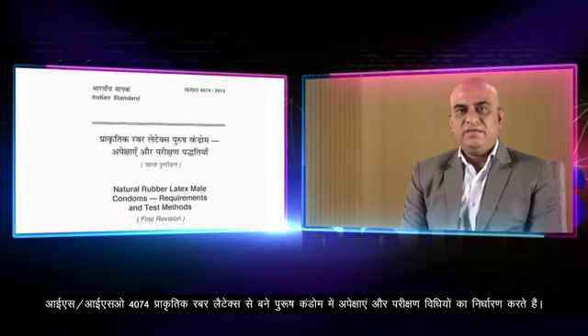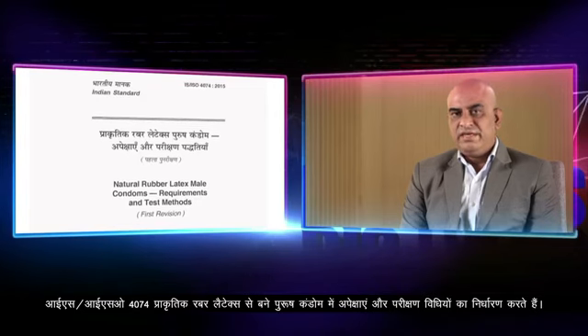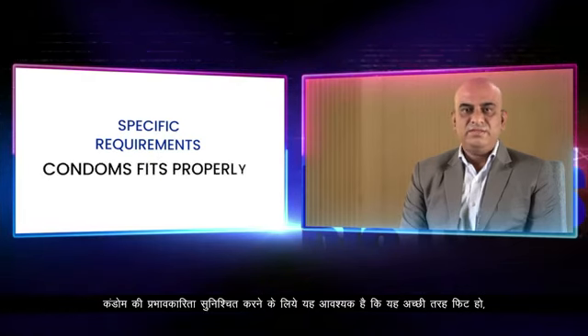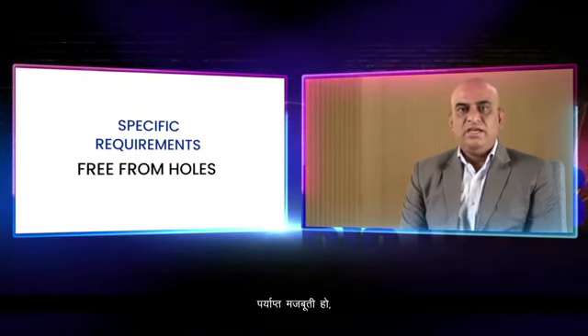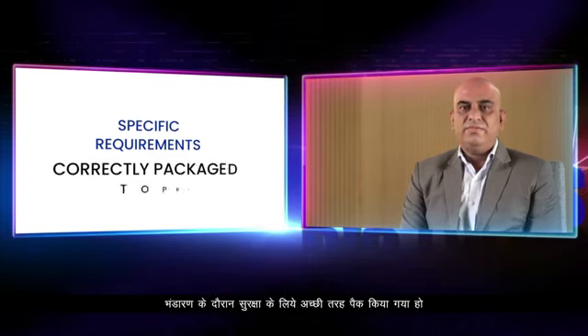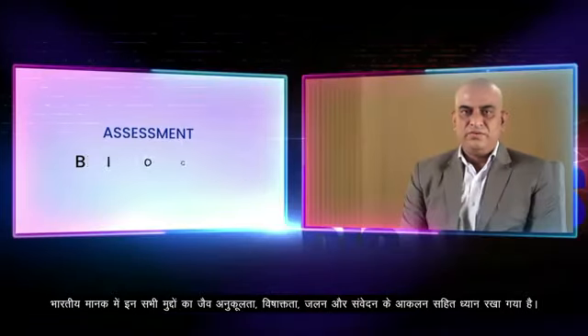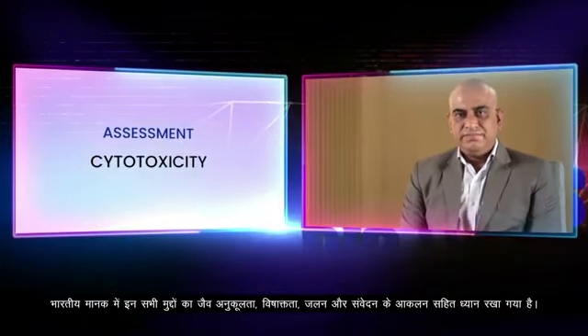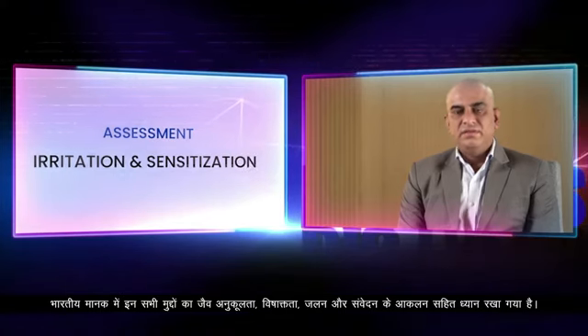ISO 4074 specifies the requirement and test methods for male condoms made from natural rubber latex. To ensure that condoms are effective, it is essential that condoms fit properly, are free from holes, have adequate physical strength, are correctly packaged to protect them during storage, and are correctly labeled to facilitate their use. All these issues are addressed in this Indian standard along with assessment for biocompatibility, cytotoxicity, irritation and sensitization. Condoms as per this standard are also required to conform to the requirements for bursting pressure and volume.